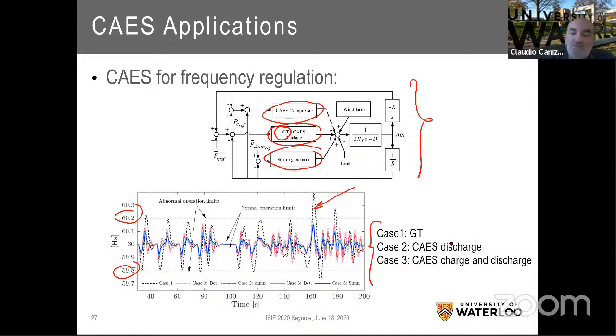Whereas if you introduce a CAES that charges and discharges to provide that regulation, like a gas turbine, you get better performance because of the fact that you have pre-compressed air that allows it to provide better, faster services in the system, as opposed to a gas turbine that basically sucks air from the system and compresses, okay, through the turbine system.